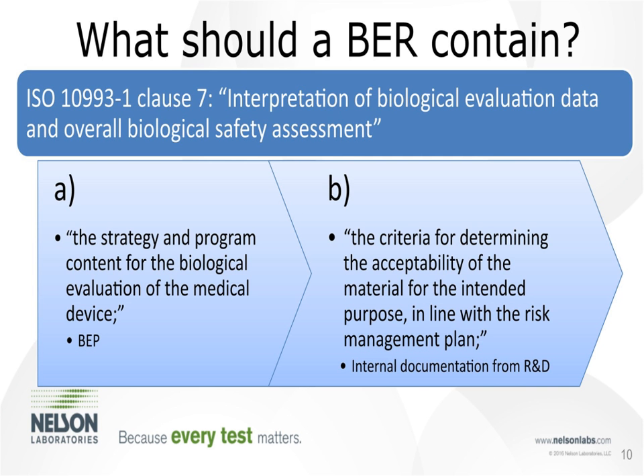Projects can be complex, and it is important to summarize your findings and present your case to your reviewers. A BER should contain specific elements outlined in ISO 10993-1 Clause 7, titled Interpretation of Biological Evaluation Data and Overall Biological Safety Assessment. They have seven points, A through G, identifying what should be included in the final evaluation.